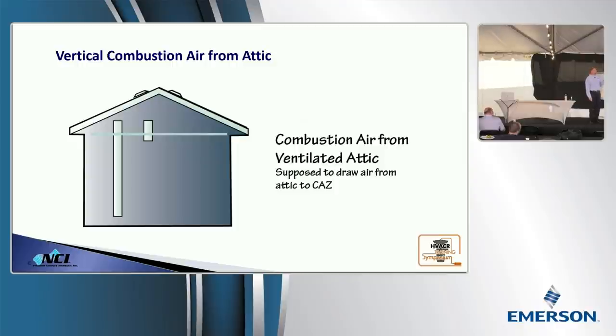Now, most attics are ventilated correctly. Is that right? Okay, now for an attic to be ventilated, unless it's foamed, if it's foamed, it gets really interesting. But let's say that attic is a standard attic, it should be ventilated. What pressure would that attic be under for air to ventilate? It'd have to be at atmospheric, probably a little negative, won't it? Because hot air rises and goes out the eaves, which means what is probably going to happen to that duct? You think air is going to go out or come in? It's going to go out.